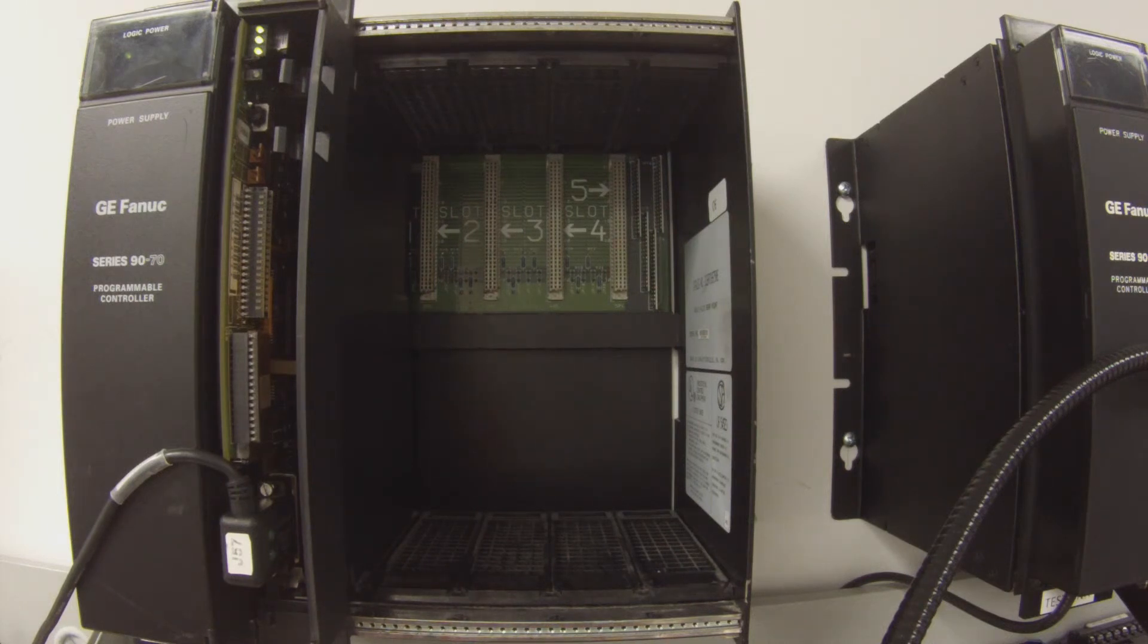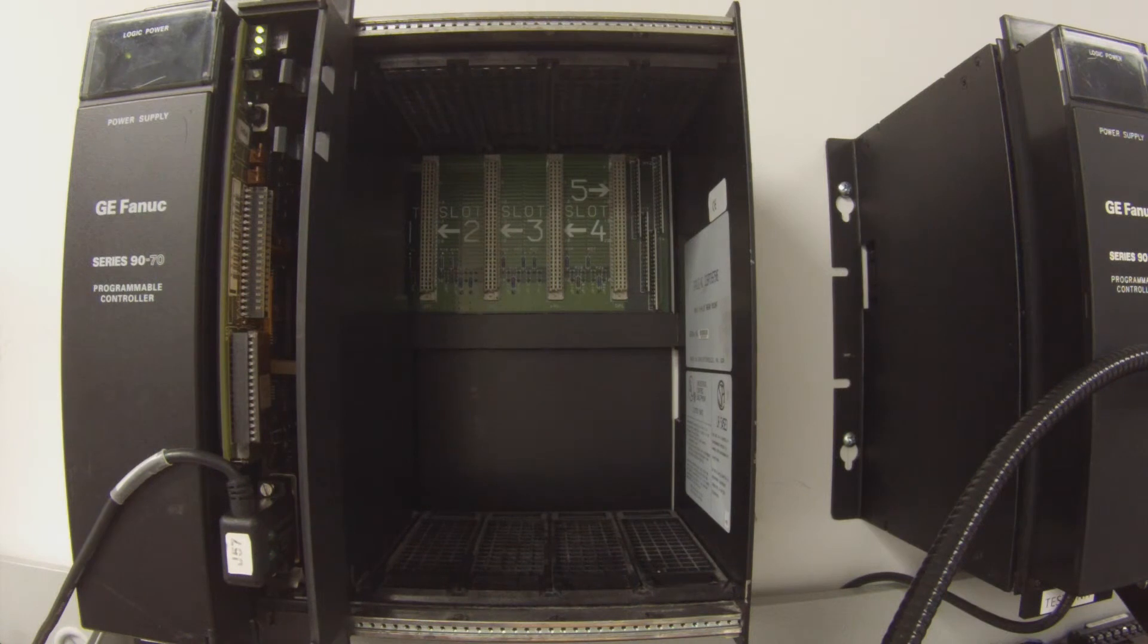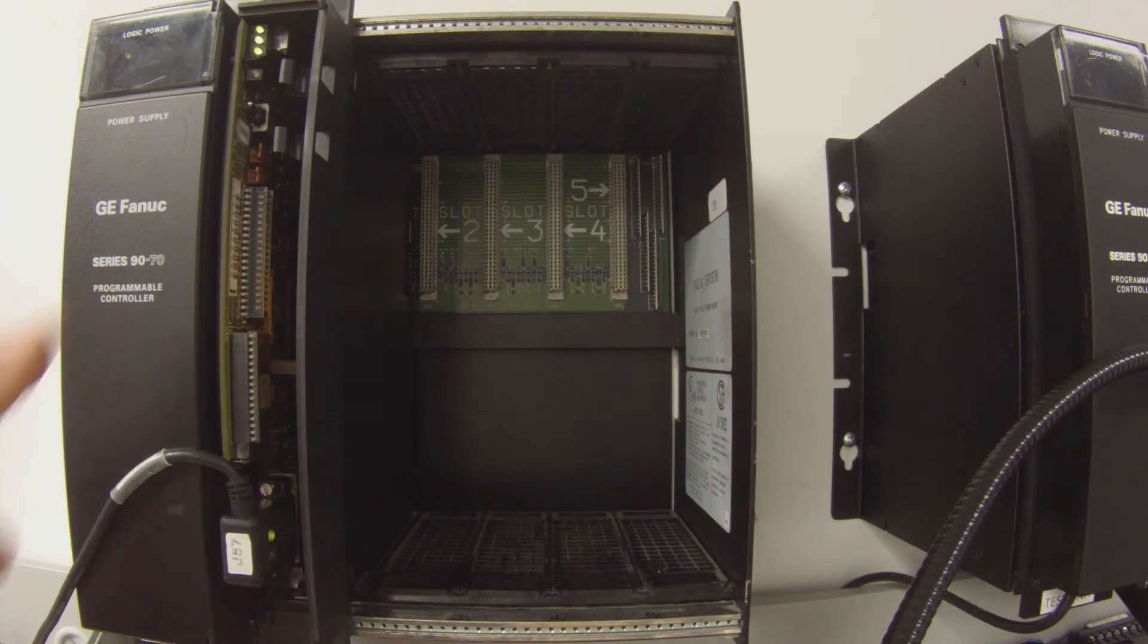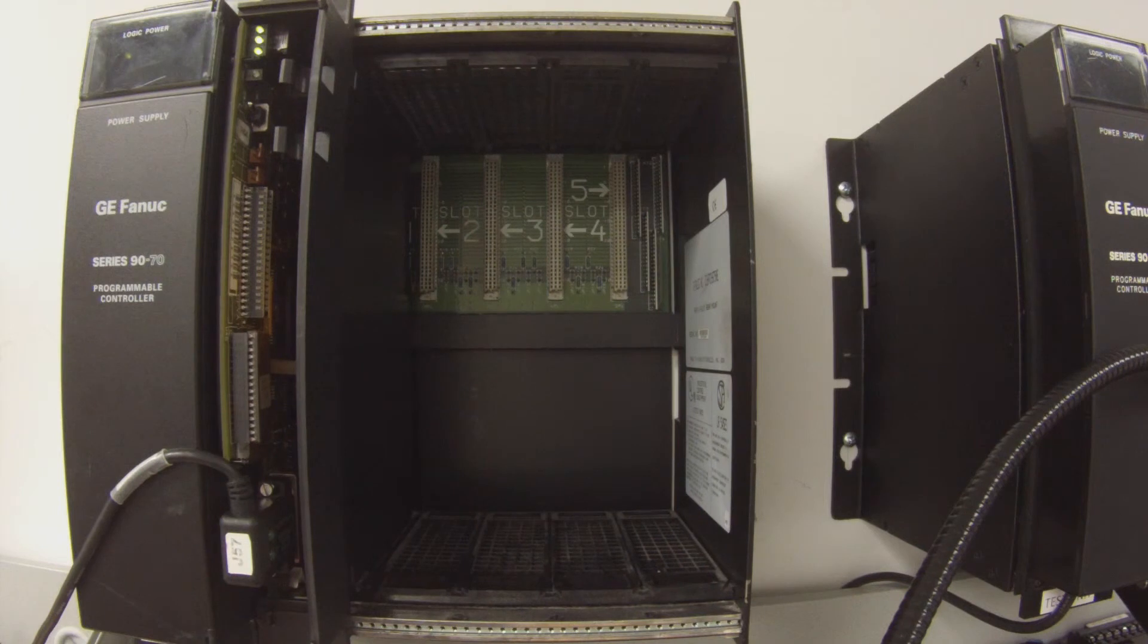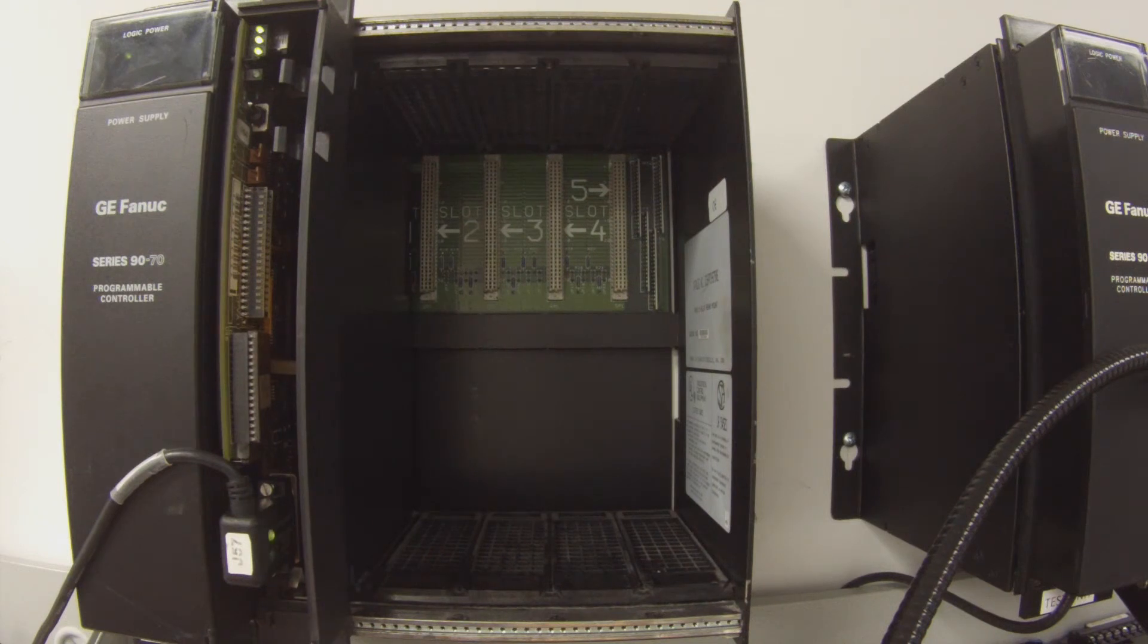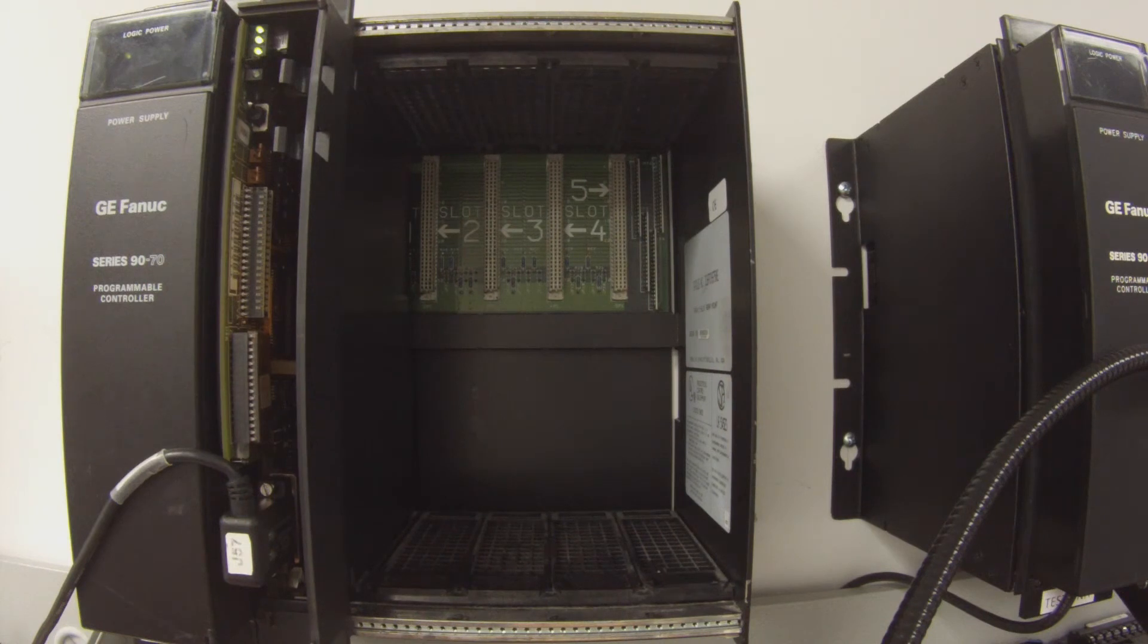So typically if we get this because they think that there is a field problem with it or if you feel that this is a processor that is giving you trouble, what we would normally recommend is that you leave it in run mode just like you see it here overnight or over a weekend, a couple, two, three days, something like that. And what you are trying to do there is that you want to see that the processor is able to hold itself in run mode for a couple of days. And if for some reason it pops out of run mode, if it fails, then there is some sort of a problem, some sort of a fault.